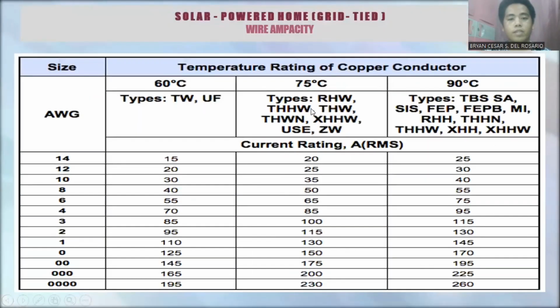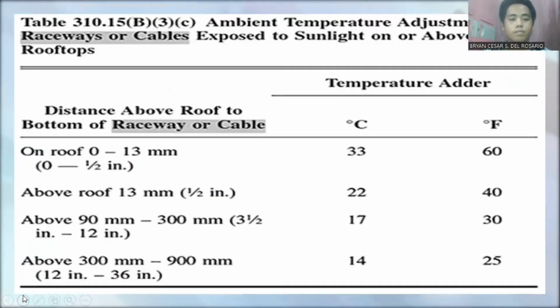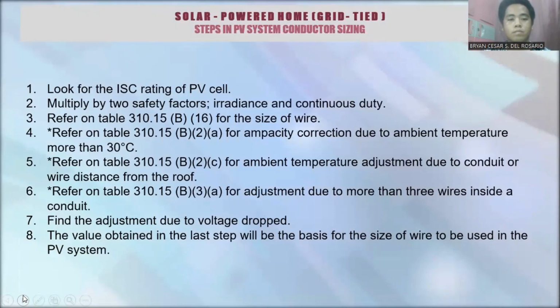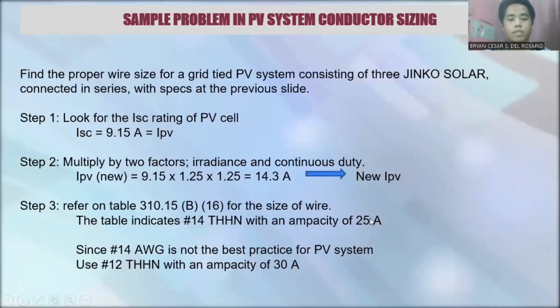Looking at the 90 degree column, we'll use THHN wire. It fits into size 14, giving an ampacity of 25 ampere. The table indicates number 14 THHN with an ampacity of 25 ampere. But since number 14 wire size is not recommended, we adjust to number 12 THHN with an ampacity of 30 ampere.